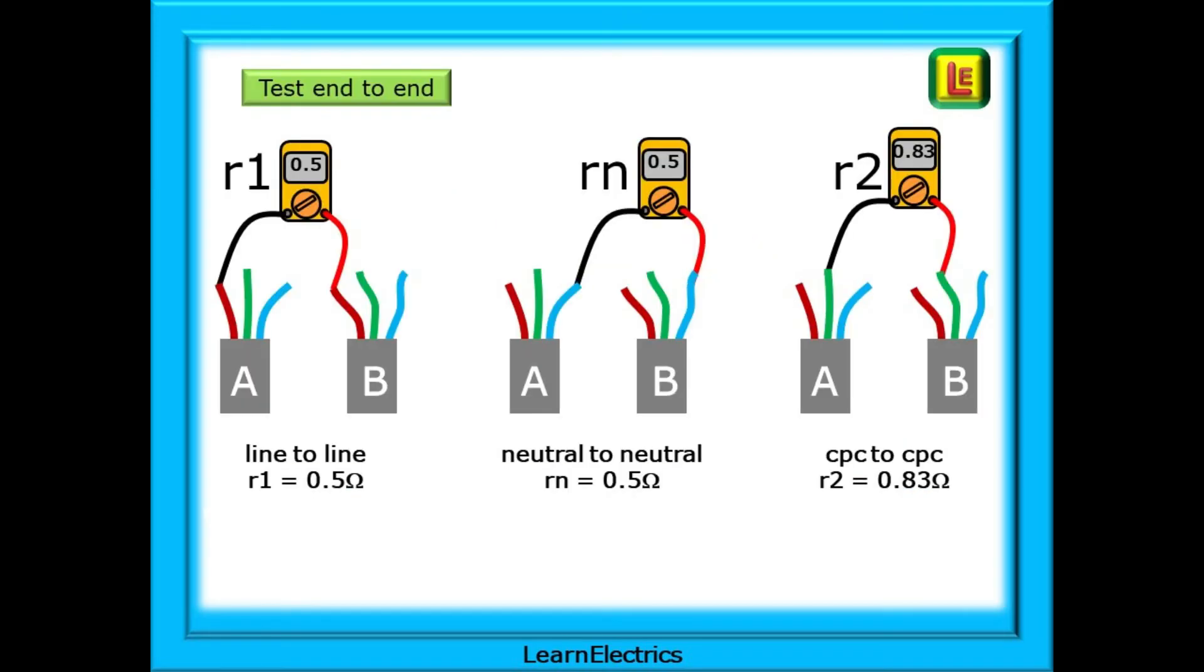Now, low ohms test between the two line conductors to get little R1, shown here as 0.5 ohms. Then test little Rn between the two neutral conductors, and you should get 0.5 ohms again. It's the same size copper as the line, and going to the same places. So it should, within reason, be the same value.